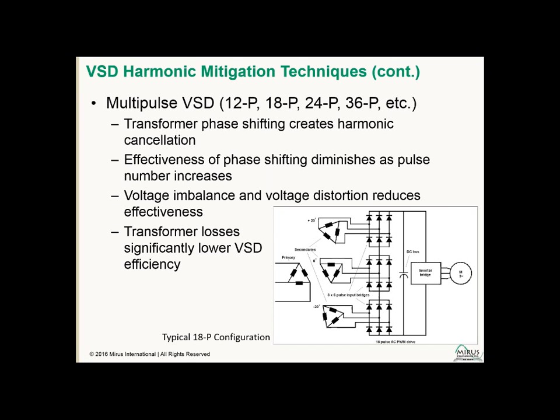And as we get into higher frequency harmonics, the phase angles vary much more, and therefore the cancellation can be minimal in many cases. Also, if you have any voltage imbalance or voltage distortion on the power system, that will dramatically reduce the effectiveness of the multi-pulse system.